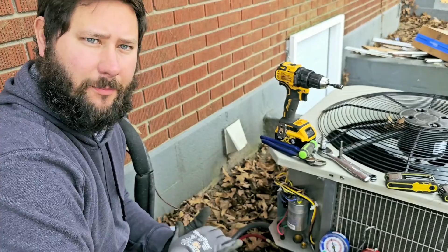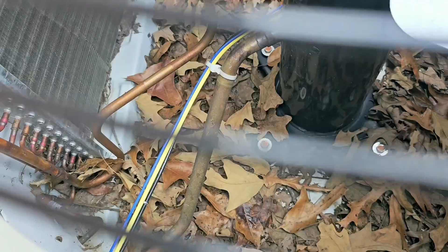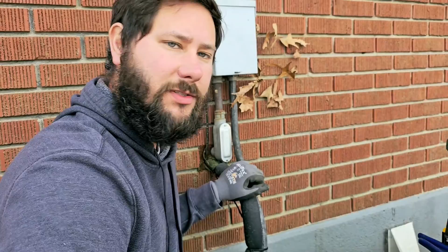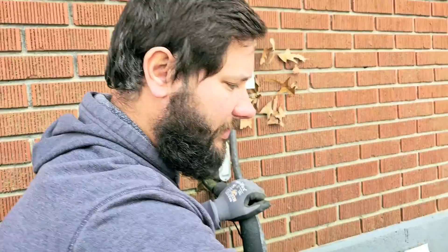Now, if you're asking yourself the question, what is the best brand? Well, it's a brand that has pressure switches. Check this out. Look inside. On the suction or the discharge, there's no pressure switches. Why do you need a pressure switch? What if the refrigerant leaks out and the compressor's running without refrigerant? There goes your compressor. So I don't know why Bryant wouldn't put a pressure switch on the suction line for the low pressure and the discharge line high pressure. I don't understand. It doesn't cost that much. It wouldn't take that much time. Come on, man.